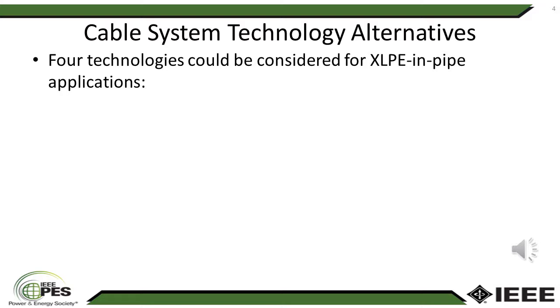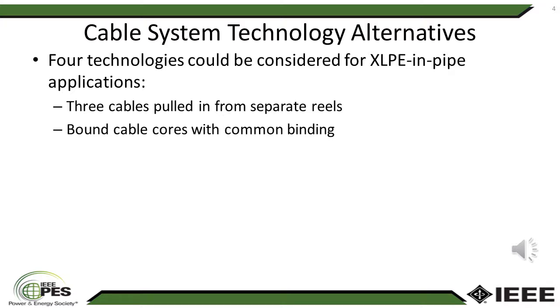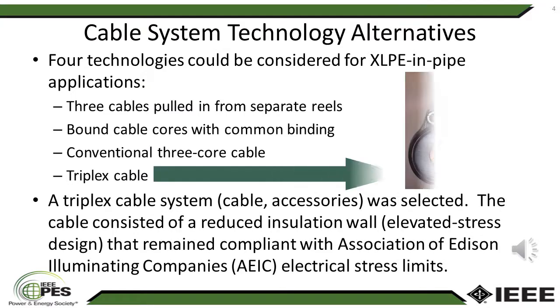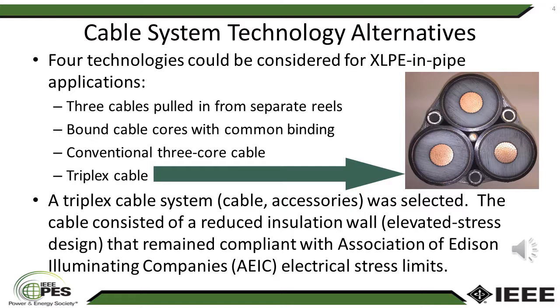As is detailed in the written paper, 4 extruded cable technologies were considered for retrofit into steel pipe. 3 cables pulled in from separate reels, bound cable cores with a common binding, conventional 3-core cable, or a triplex cable design. Ultimately, a triplex cable design was selected. This consisted of a reduced insulation wall that remained compliant with Association of Edison Illuminating Companies electrical stress limits, with a ground path that consisted of a copper conductor and 3 aluminum tubes to provide a ground continuity path.